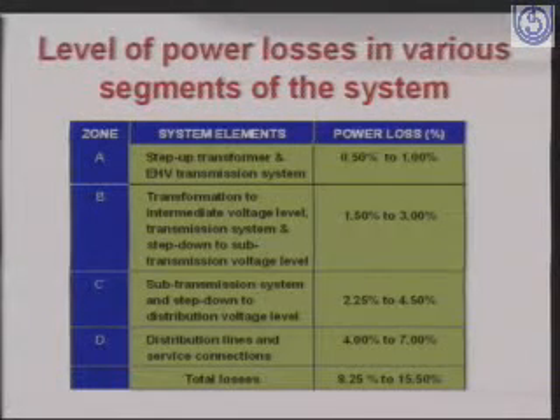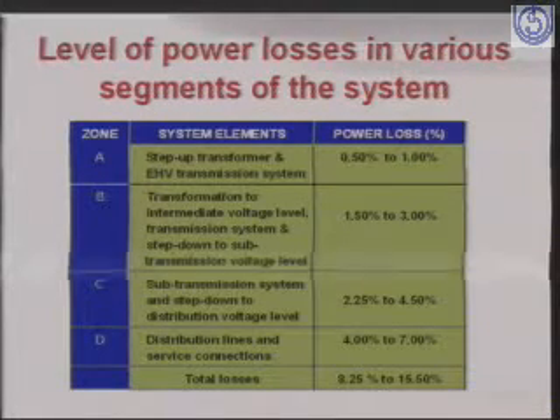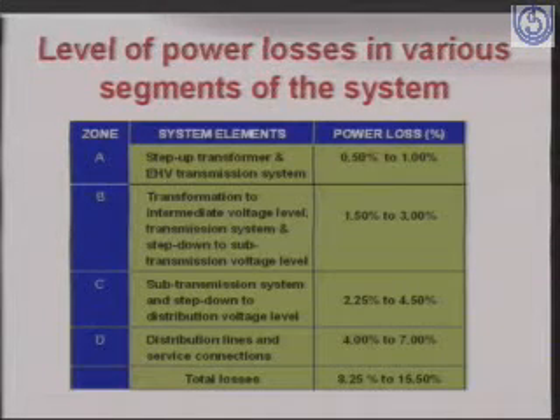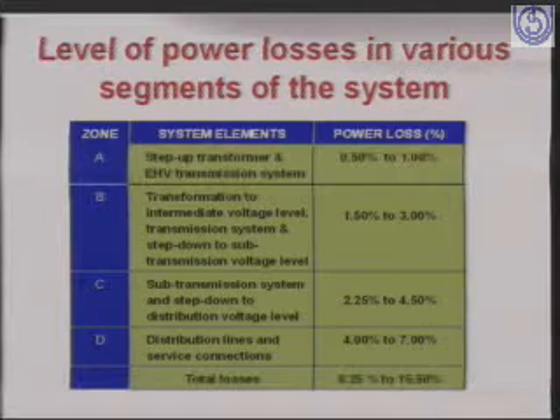Now the level of power losses in various segments of the system. These are estimates, because we have switchgear systems for which it is very difficult to assess such losses. So on average, these are the estimates one can presume. Step-up transformers and extra high voltage transmission system losses should be within the range of 0.5 to 1%. Then transformation to intermediate voltage level transmission system and step down to sub-transmission voltage level, the losses can be in the range of 1.5 to 3%. In the other sub-transmission system and step down to distribution voltage level, the losses could be in the range of 2.25 to 4.5%. And finally, in the distribution lines and service connection, the losses could be 4 to 7%.